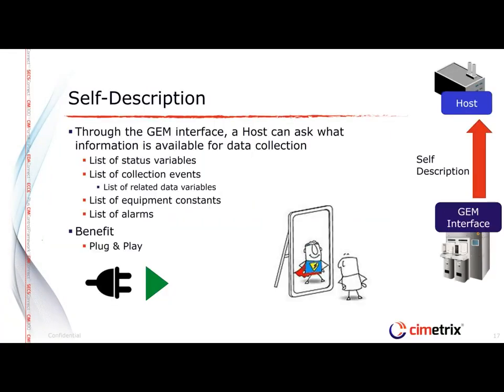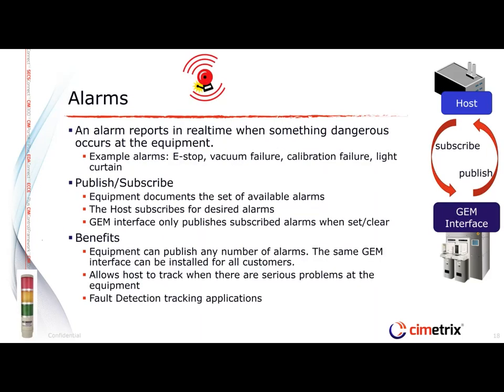There's also some self-description functionality in a GEM interface, where through the GEM interface the host system can ask for a list of collection events that are available, status variables, data available with the collection events, as well as equipment constants and alarms. Those are all published through the GEM interface to facilitate plug-and-play applications.